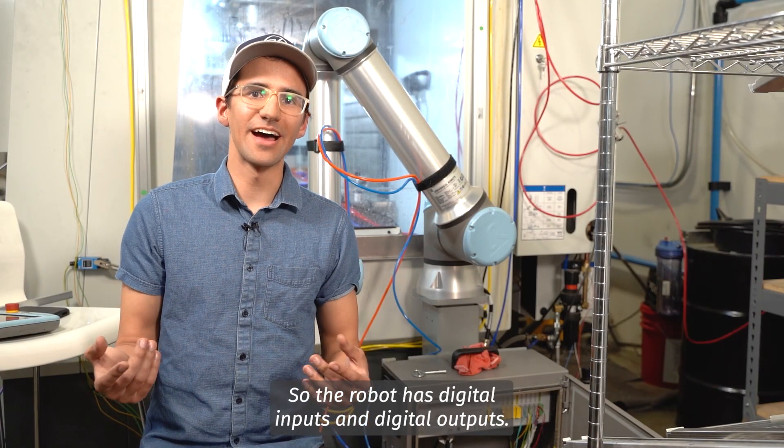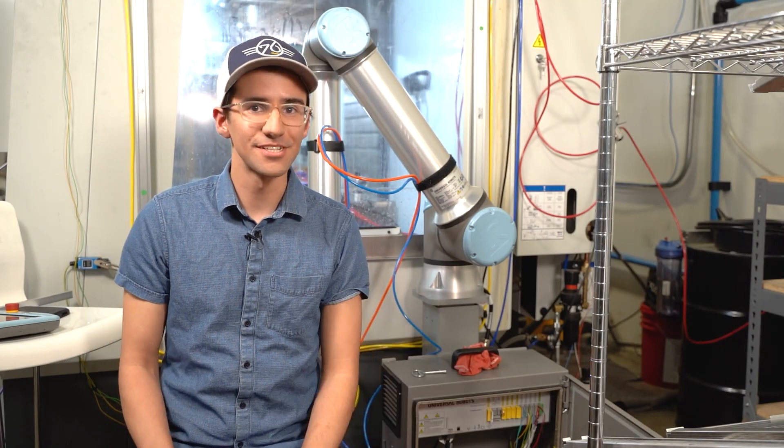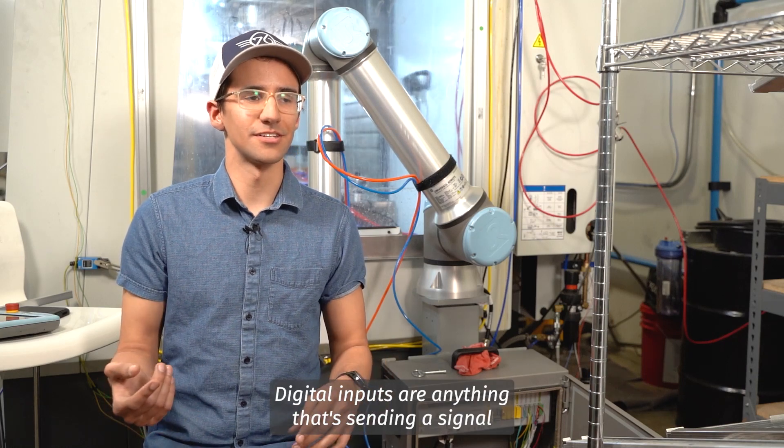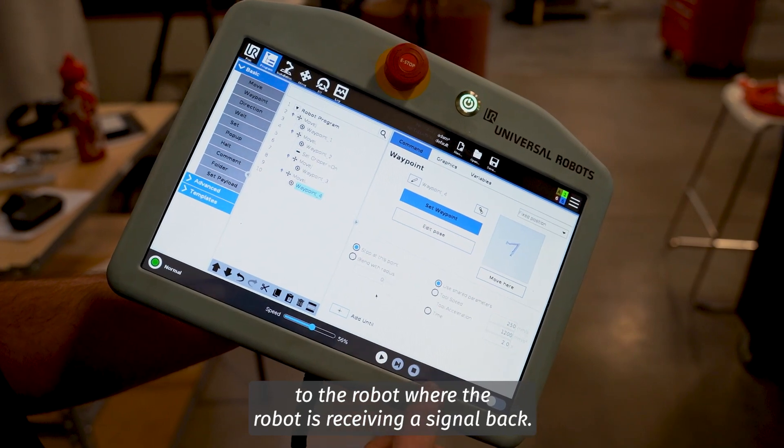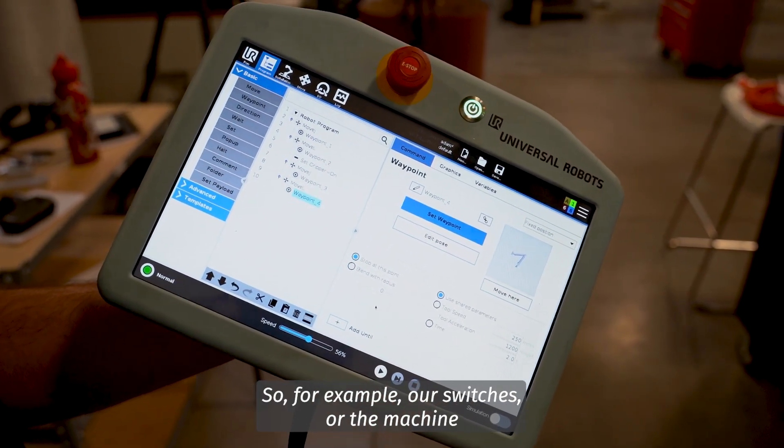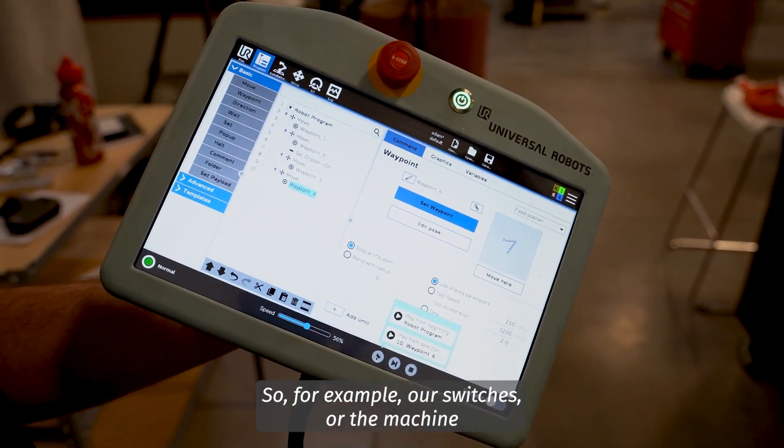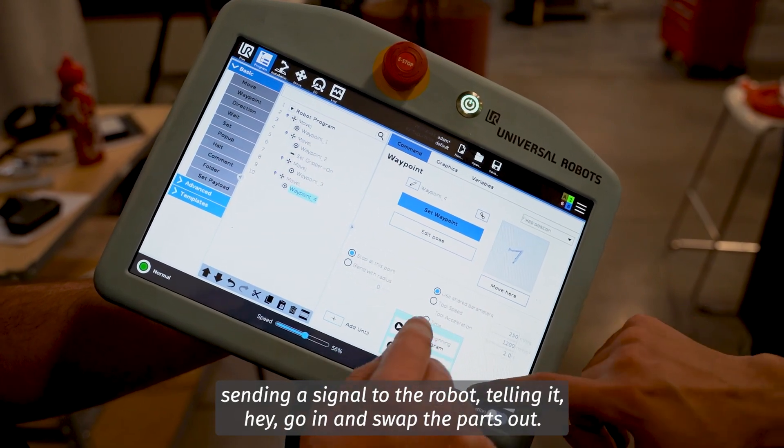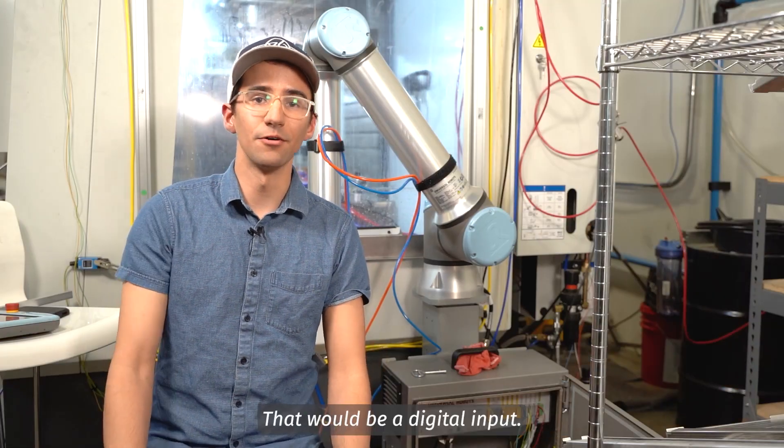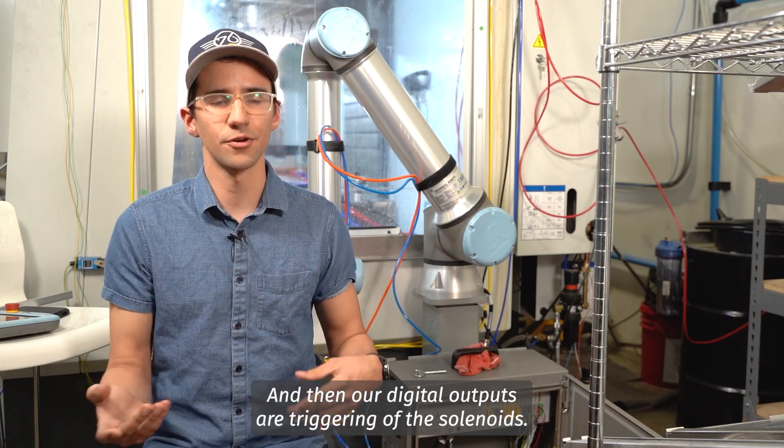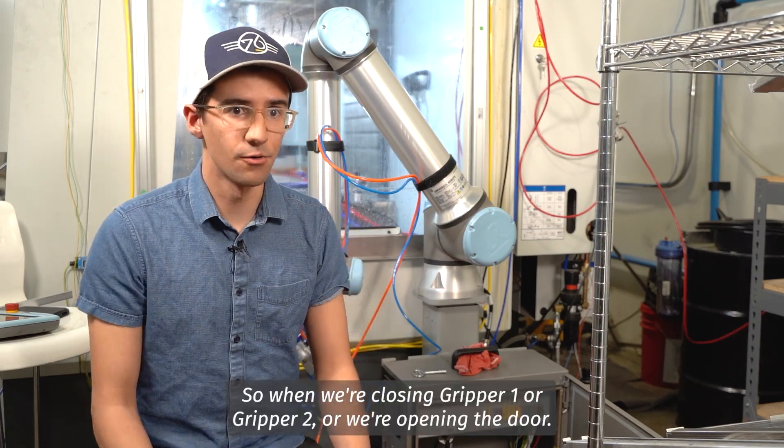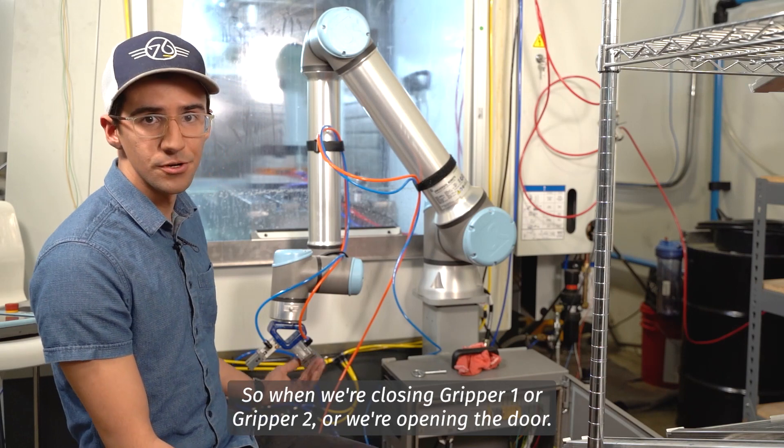So the robot has digital inputs and digital outputs. Digital inputs are anything that's sending a signal to the robot where the robot is receiving a signal back. So for example, our switches or the machine sending a signal to the robot telling it, hey, go in and swap the parts out, that would be a digital input. And then our digital outputs are triggering of the solenoids, so when we're closing gripper one or gripper two, or we're opening the door, that's all going to be a digital output.